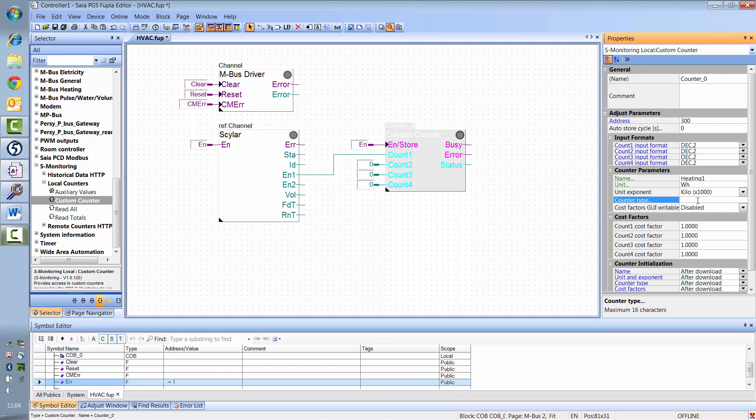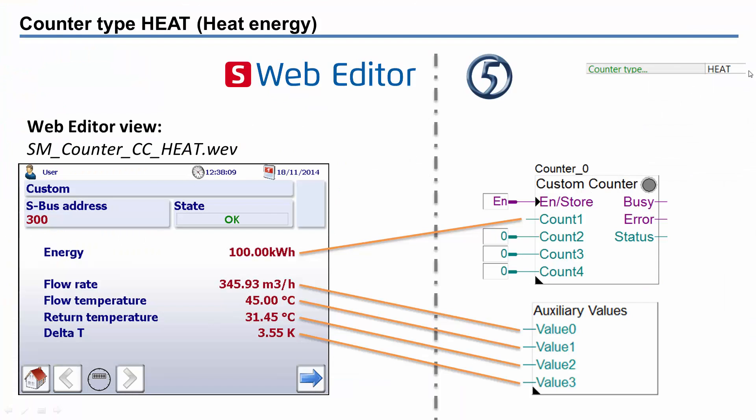The S-Monitoring function offers ready-made templates for various counter types. In our case, we have a heat meter with the heat template. For the counter type heat, the web editor already has ready-made templates. Simply link the meter's value to the relevant input on the F-box and it will automatically be visualized.